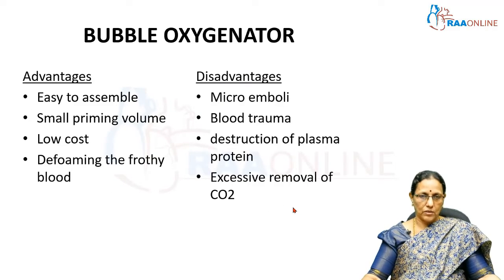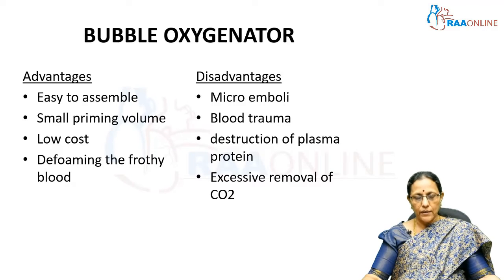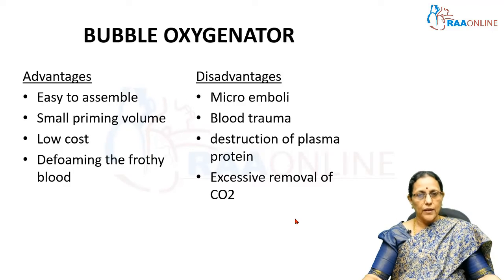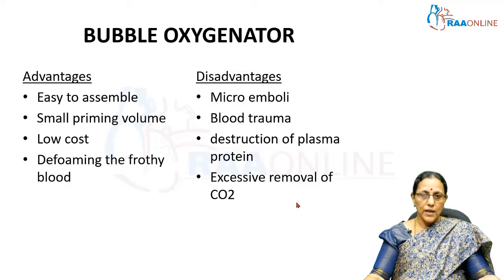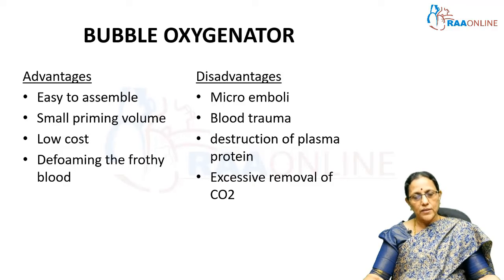What were the disadvantages of a bubble oxygenator? Since there was direct interface of gas and blood, blood trauma was more and plasma protein destruction was also seen. Though there were advantages like easy assembly and lower cost, because of direct bubbling of oxygen the pCO2 could not be controlled and the pO2 also could not be controlled — there was hyper-oxygenation and excess removal of carbon dioxide. So carbon dioxide removal could not be maintained with this bubble oxygenator, and researchers wanted to develop a more physiological oxygenator.